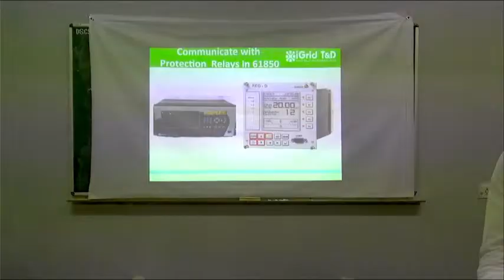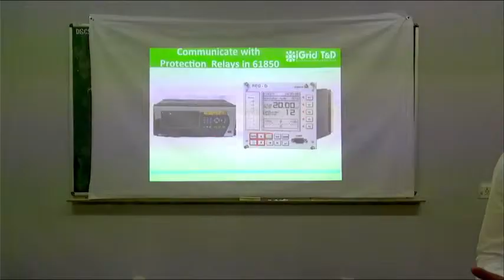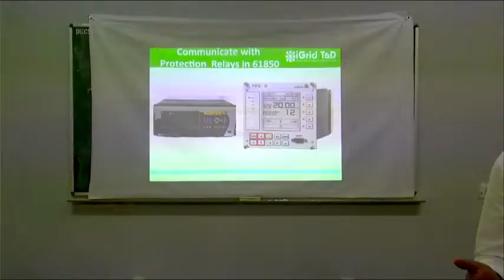In addition to that, there are protection relays. We saw that we read the data from the bay control unit, and then we also read the data from the protection units. Again, there are different types of relay. It can be a distance protection relay, or if it is a transformer panel, it will be a differential relay. And if we have to read the data from an RTCC panel, wherein I want to see the tap position, winding oil temperature, all these things, that also we can read from a transformer relay.